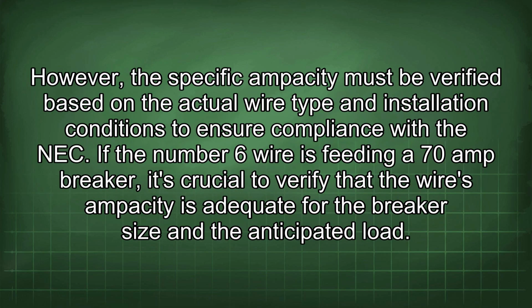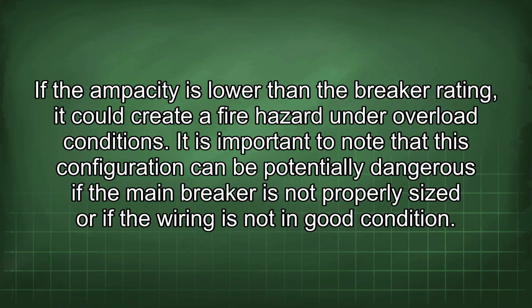However, the specific ampacity must be verified based on the actual wire type and installation conditions to ensure compliance with the NEC. If the number 6 wire is feeding a 70-amp breaker, it's crucial to verify that the wire's ampacity is adequate for the breaker size and the anticipated load. If the ampacity is lower than the breaker rating, it could create a fire hazard under overload conditions.